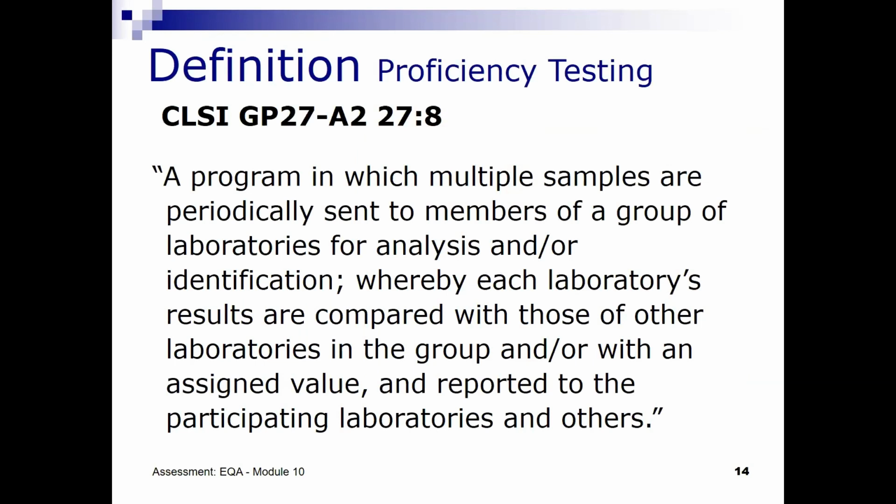All right. We have one question on the retesting. Can you clarify what the difference is between retesting and rechecking? Yes, it's about scope. Retesting assumes that you're doing 100% of the work again. So all the work gets read at the local lab, and then all gets sent to some reference lab, and the lab repeats all the work. It's less common now, but in earlier times with rapid HIV testing, that was the method. And then rechecking is a random selection of a small amount, usually 10% of tests, that are retested. So retesting is 100%, rechecking is some smaller number, say 10%.